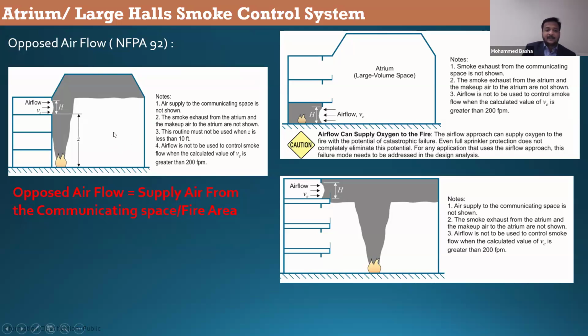So the difference between this and this, you can see the fire location. In this one, the fire is located at the corner. Basically, here only one communicating space is there. So we do not want the smoke to go out from this space. Whereas in this condition, the fire is located somewhat far away from the communicating space, and all the spaces are open to each other. Why are they pressurized? Why are they forcing the air only from the top? Why is it not at the bottom?